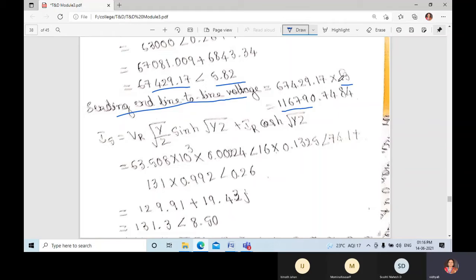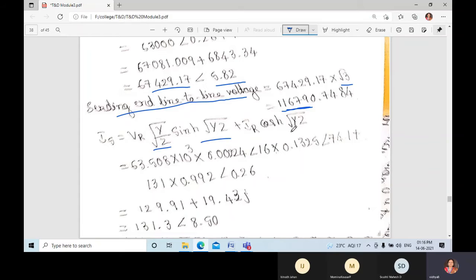The sending end line-to-line voltage is approximately 116,790.748 V, or about 1 lakh 16 thousand 790.748 volts. For Is, using Is = Vr·√(Y/Z)·sinh(√YZ) + Ir·cosh(√YZ), substituting all known values gives Is = 131.3∠8.50°.